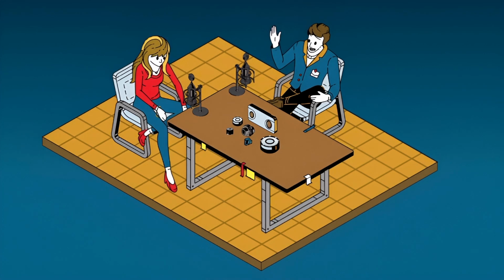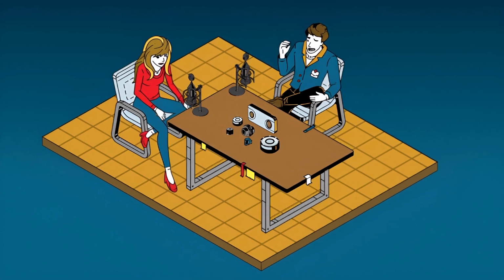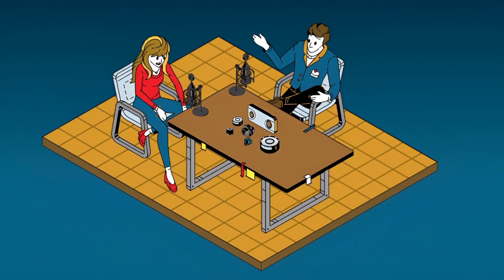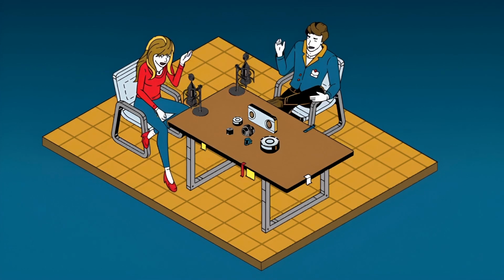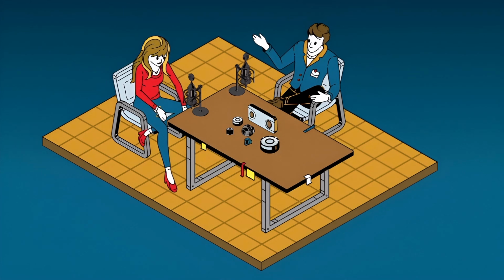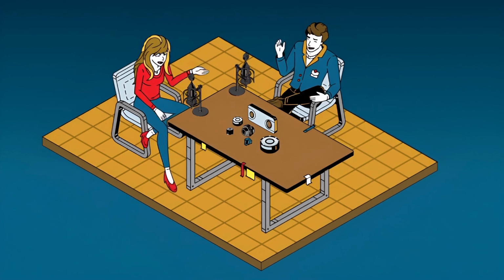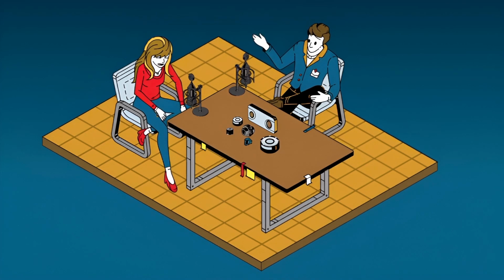Like if you're pushing it hard. Exactly, if it's seeing extreme loads, maybe close to its capacity, or operating in a really harsh environment - temperature swings, vibration, moisture - or just used constantly, day in, day out. Heavy usage cycles, any of those things would probably mean you need to calibrate more frequently than once a year to maintain accuracy, maybe every 6 months, maybe even more often in some critical cases.